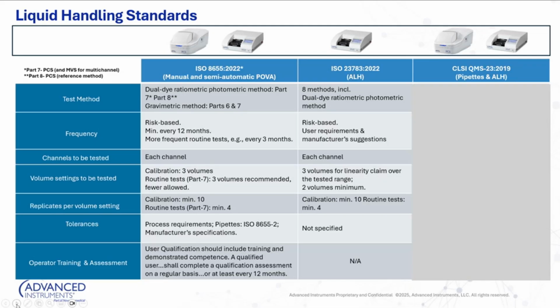So with regards to the test method options for automated liquid handlers, there are 8 different methods included in 23783, including the dual dye ratiometric photometric method, which is where our systems come into play. Now, with regards to frequency, it's a little bit different for automated liquid handlers. It's a risk-based evaluation. So how often do you test that automated liquid handler? It could be quarterly, every 6 months, or annually. What's the acceptable amount of risk if it's not delivering the correct volume? But then maybe you also have some user requirements or even manufacturer suggestions that you follow.